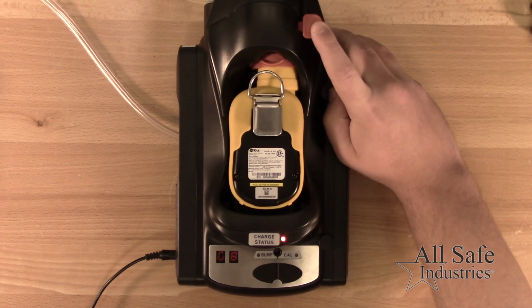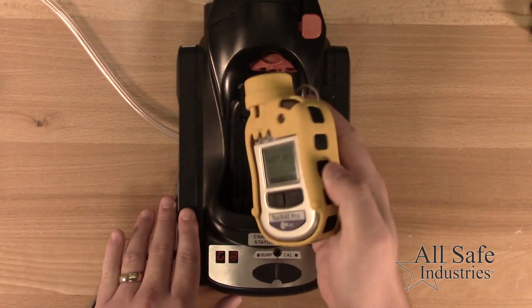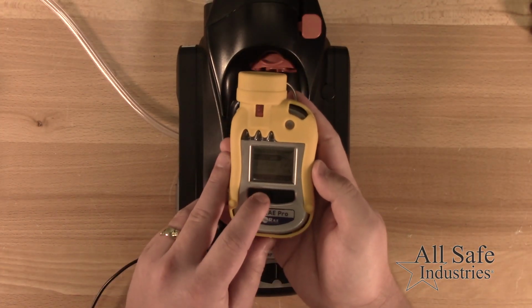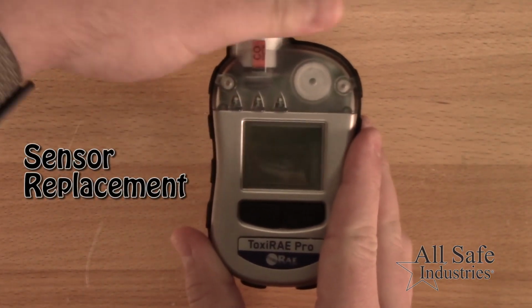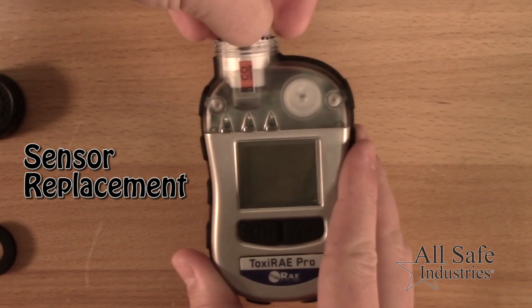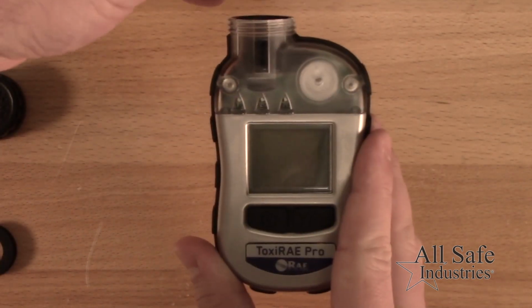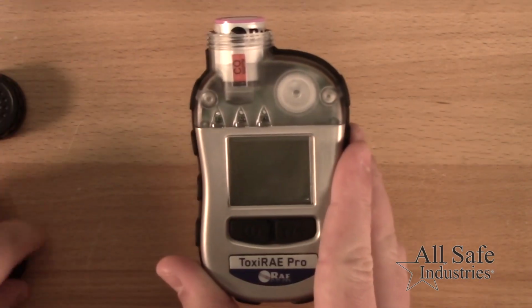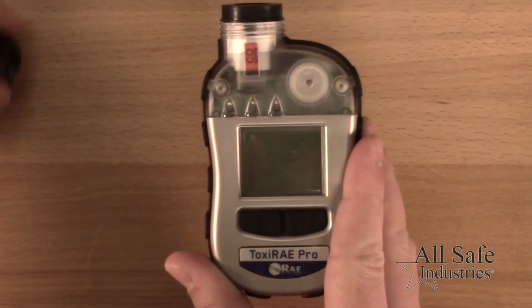Press the red trigger to release the meter from the cradle, remove the meter, and read the display for the results of the calibration. To replace a sensor that fails calibration, unscrew the cap assembly and gently lift out the sensor and replace, being sure to properly align the pins. Reattach the cap assembly and recalibrate.